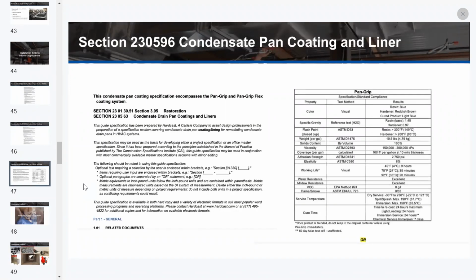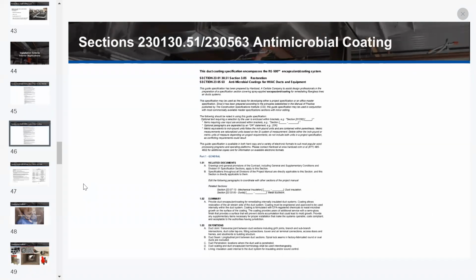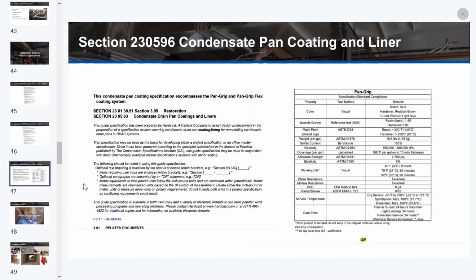Section 230-130, antimicrobial coating. These specifications are related to products that are used to coat fiberglass. The coating locks down the friable liner. So in an existing building that has fiberglass insulation in the duct system where you're getting particles and material coming out of the duct system, you can go in, do an actual duct cleaning, and then coat over that, lock down those fibers, and keep them from getting back into the airstream. It gives you a much cleaner system.